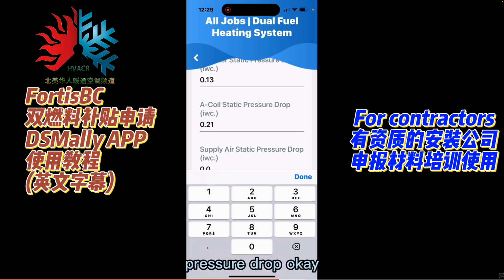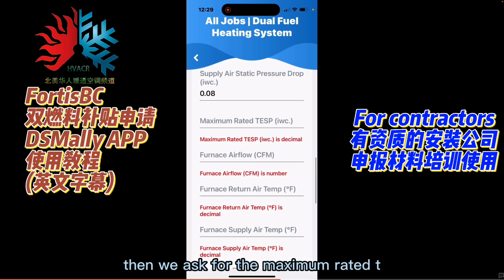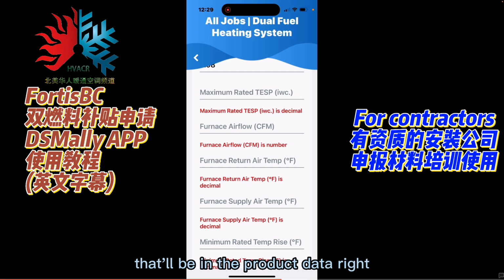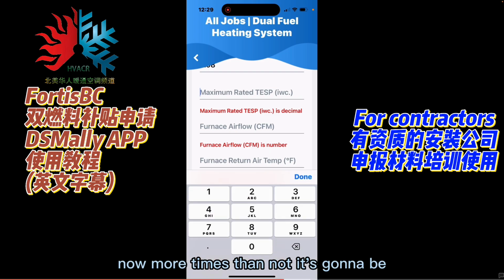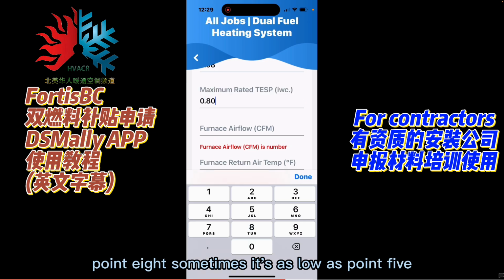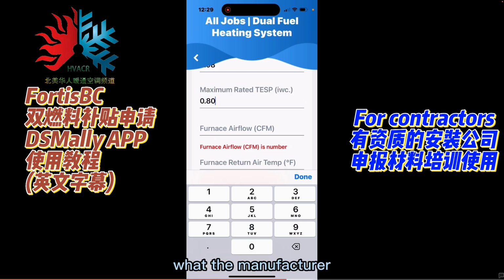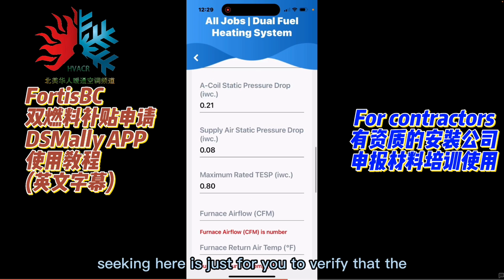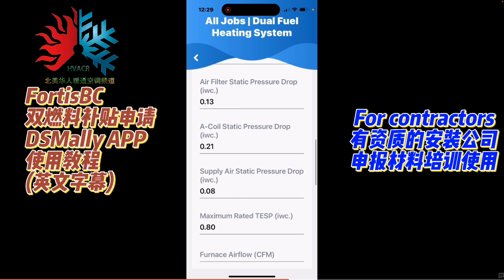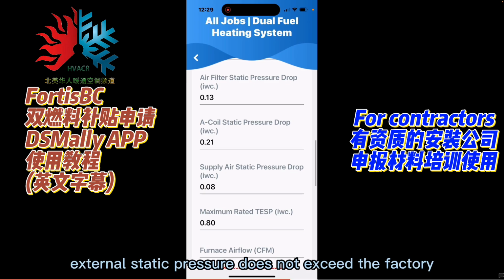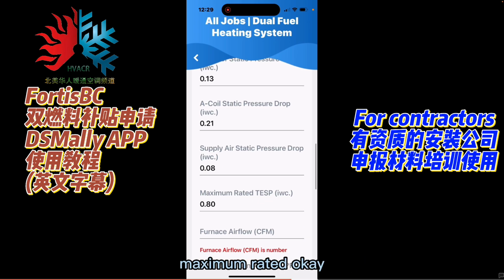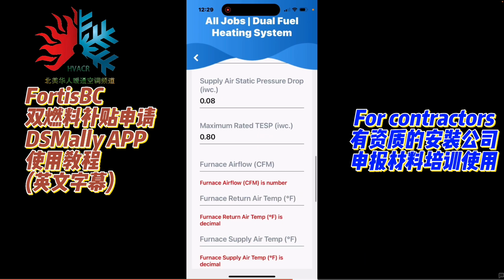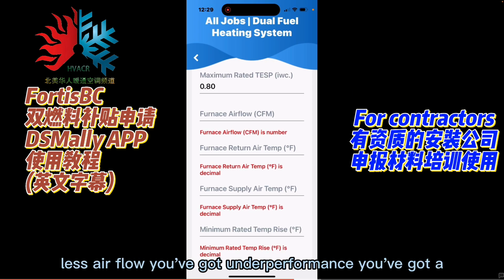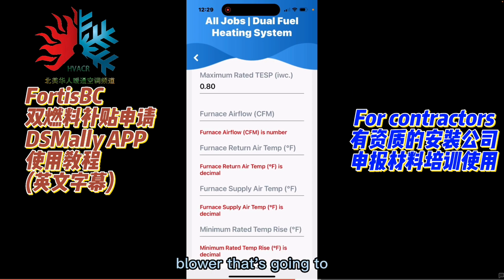pressure drop, okay. Then we ask for the maximum rated total external static pressure. That'll be in the product data, right in the install manual. Now, more times than not, it's going to be 0.8. Sometimes it's as low as 0.5. But again, what the program is seeking here is just for you to verify that the measured total external static pressure does not exceed the factory maximum rated, okay? Otherwise, you've got a lot of problems. You've got a lot less airflow, you've got underperformance, you've got a blower that's going to give out shortly, and so on and so forth.